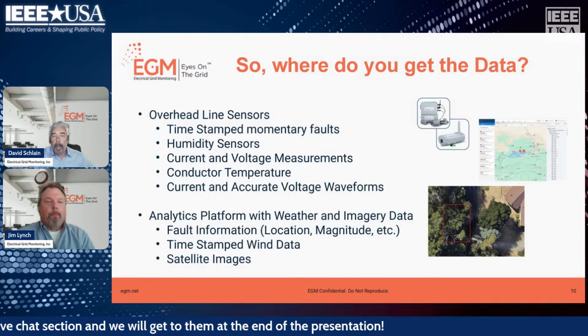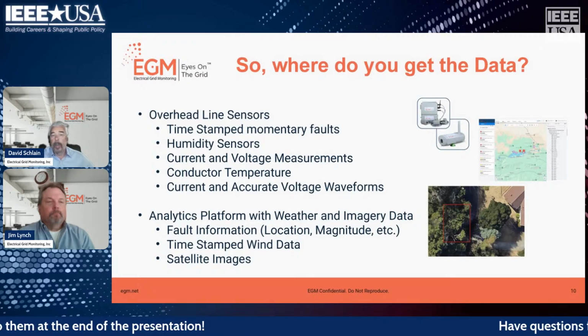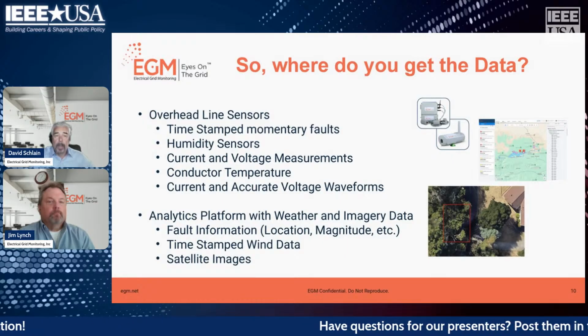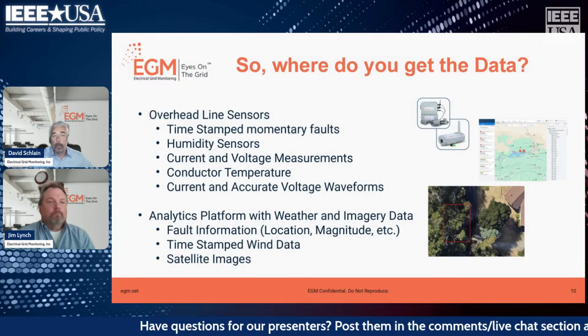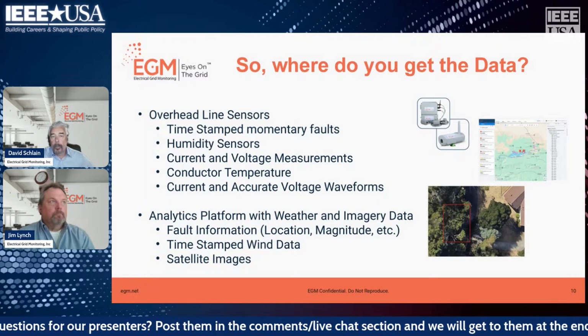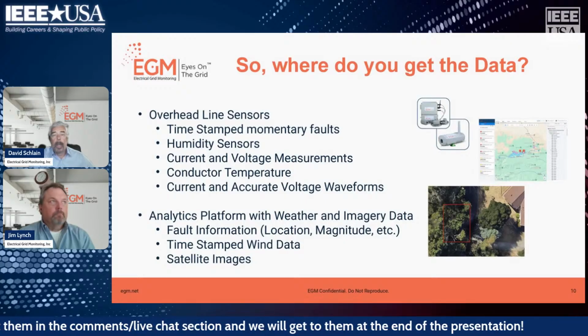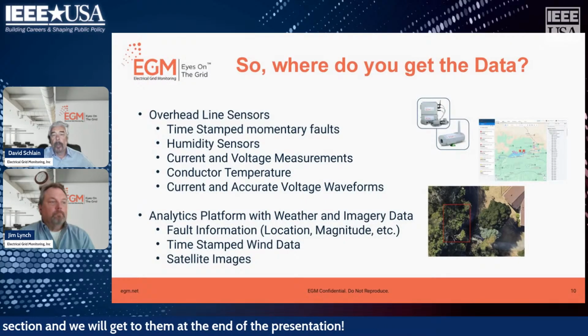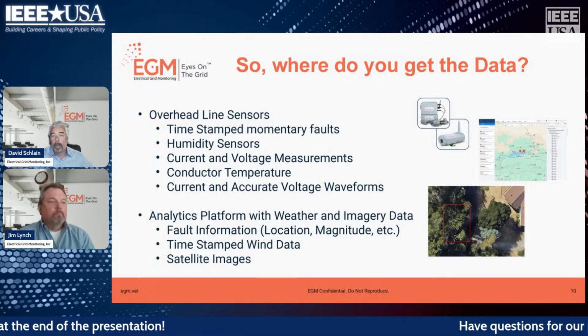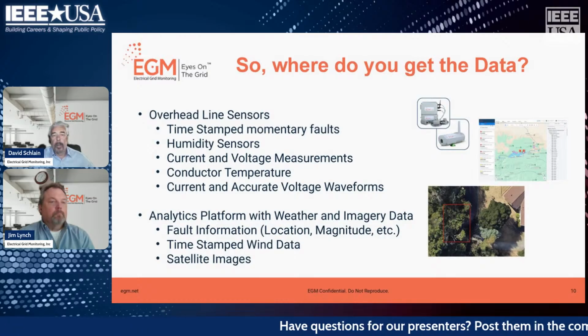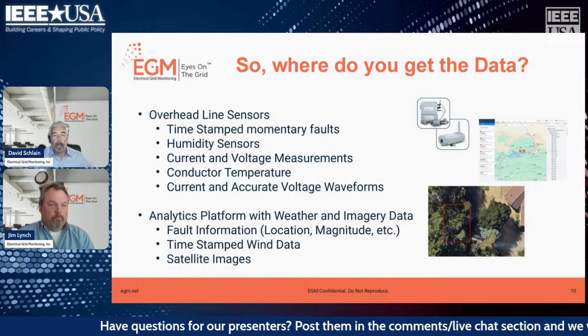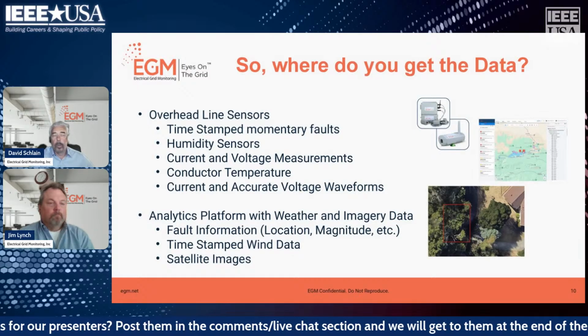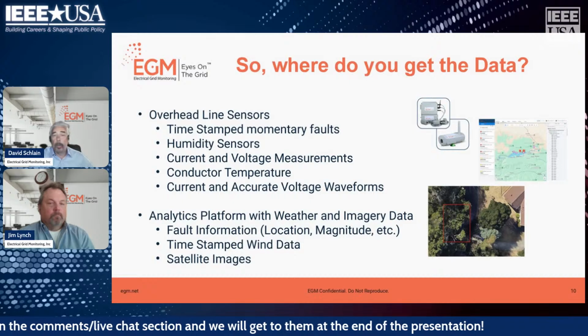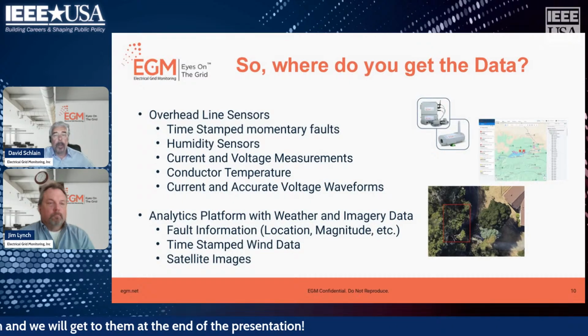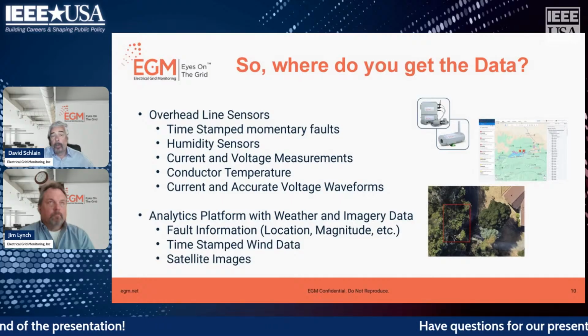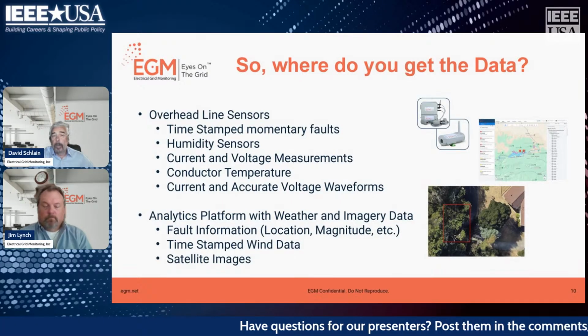This information is collected by analytics platforms, which then notify utilities of those issues. The line sensors are essentially a combination of intelligent communicating computers hanging on a line and oscilloscopes. They provide waveforms, and power engineers can use those waveforms to detect momentary faults and anomalies occurring from vegetation encroachment, equipment effects or looming equipment failure, animals running on the line, or birds landing on it. They all create noise, or what I call useful noise, in the system that our sensors can detect.